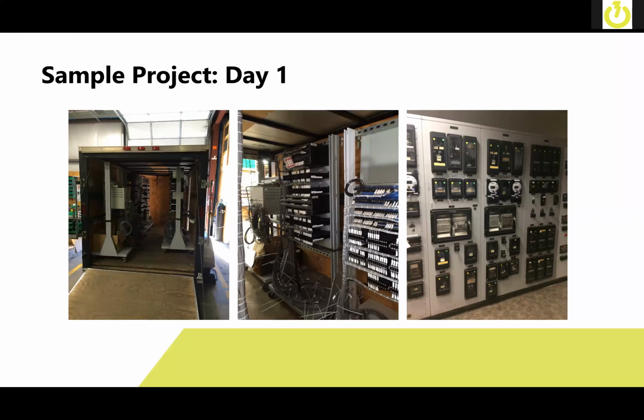You can see there's a whole bunch of older equipment in there, electromechanical relays, and very limited fault location and disturbance analysis capabilities in those relays. A lot of times, all you have is just a little flag and it tells you that it tripped. But whether it was the primary cause of the trip, what phase it actually was on, how long the event duration took, whether the relay was supposed to operate even, cannot be determined from that because all you have is just a flag.